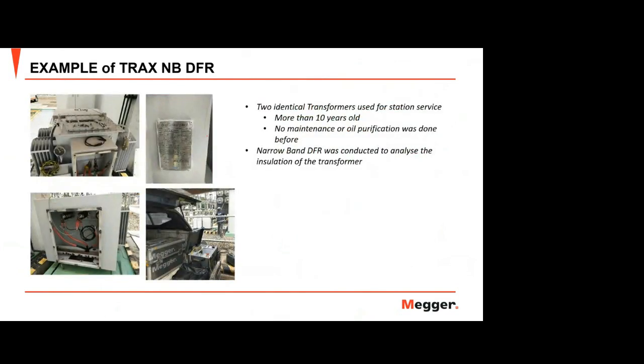So in this example here, the customer used TRAX with narrowband DFR. They tested 2 identical transformers for station service. This transformer is more than 10 years old. No maintenance or oil purification was done before.